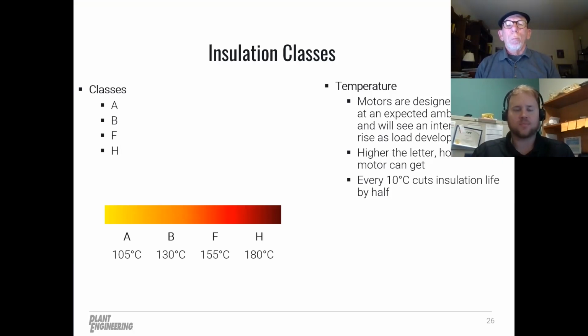And that's where we come back to NEMA. We mentioned them before, the National Electrical Manufacturers Association. Another group that we haven't mentioned yet is the International Electrotechnical Commission. That's IEC, basically NEMA's counterpart, but in Europe. Both NEMA and IEC have standardized operating temperatures, and we call those insulation classes. Motors will always be rated with an insulation class. We talked earlier about the nameplate data. That's something you can find directly on the nameplate. And what that insulation class applies to is the insulation on the windings.